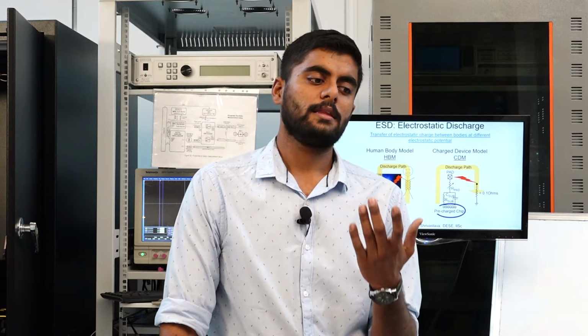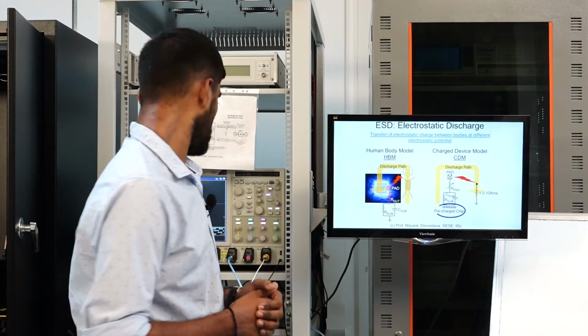So IEC 61000-4-2 then lays down the characteristics and the parameters that have to be qualified for ESD reliability in bigger systems. So HBM, CDM, and MM follow the component level or device level testing, and this IEC then follows a system level testing. So this is more about ESD in a very nutshell.